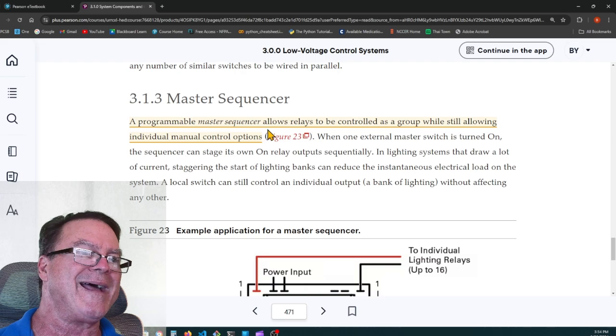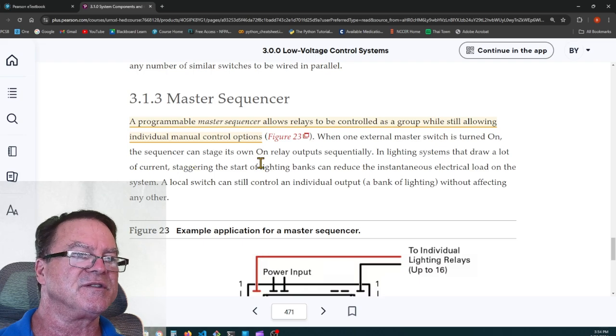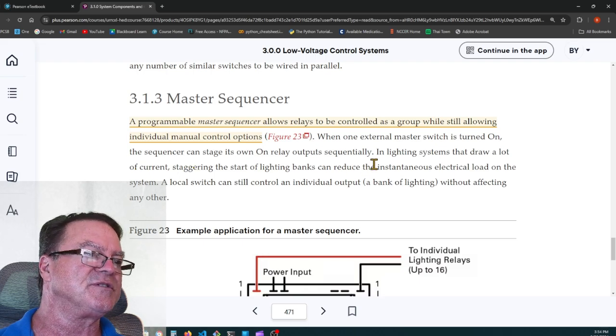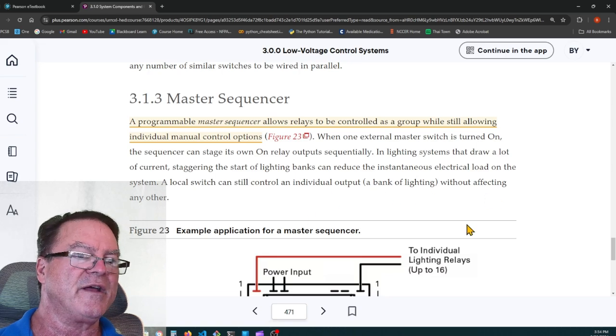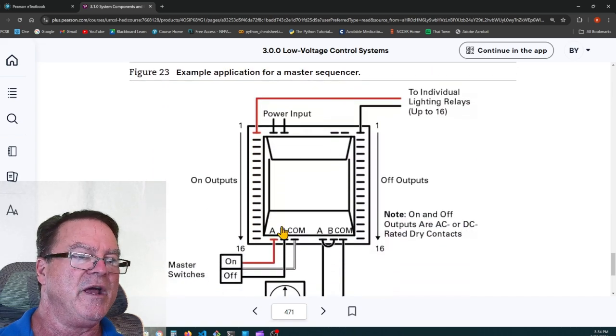It says a programmable master sequencer allows relays to be controlled as a group while still allowing individual manual control operations. When one external master switch is turned on, the sequencer can stage its own on-relay outputs sequentially. In lighting systems that draw a lot of current, staggering the start of lighting banks can reduce the instantaneous electric load on the system. A local switch can still control an individual output or a bank of lighting without affecting any other. So here they may have several different outputs.